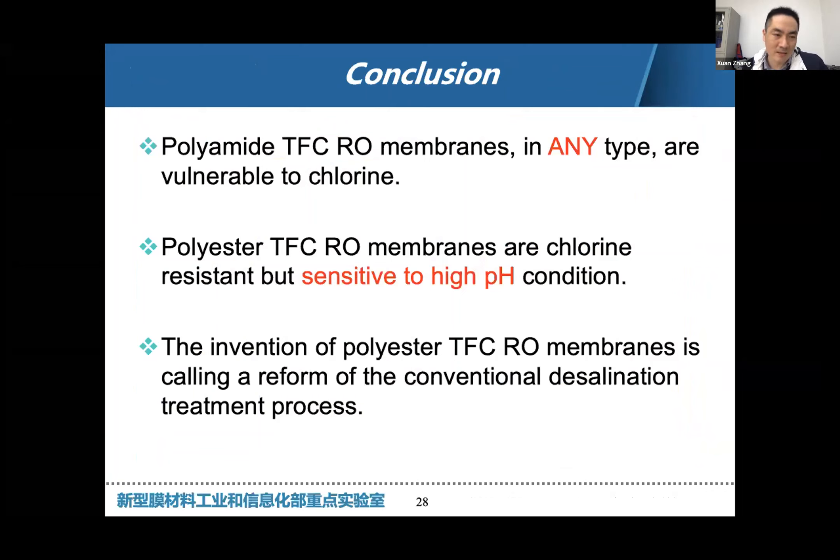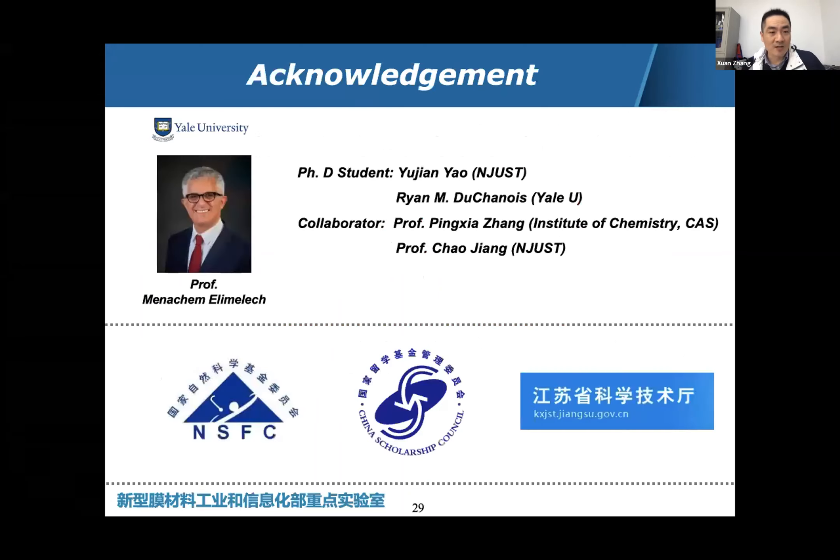In conclusion: polyamide membranes are still good for desalination, but they are vulnerable to chlorine in any type. Our polyester membrane is inherently chlorine-resistant, but its drawback is sensitivity to high pH — at pH 8, 9, 10, or higher, polyester will degrade. Third, because we now have a chlorine-resistant membrane, I believe it is time to reconsider the construction or reformation of the desalination plant. Finally, I would like to thank my collaborator Professor Menachem Elimelech at Yale University and other collaborators, and also thank the funding support.